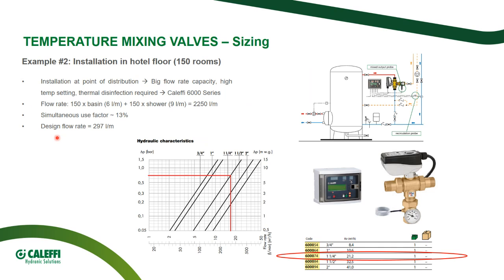Now, let's calculate the flow. We just said we have 150 rooms. If we forget for a moment the kitchens and other service rooms, and consider just the real hotel rooms, we have 150 basins and 150 showers. So the total sum is 2,250 liters per minute. For this size of hotel, the simultaneous use factor given by the table is around 13%.